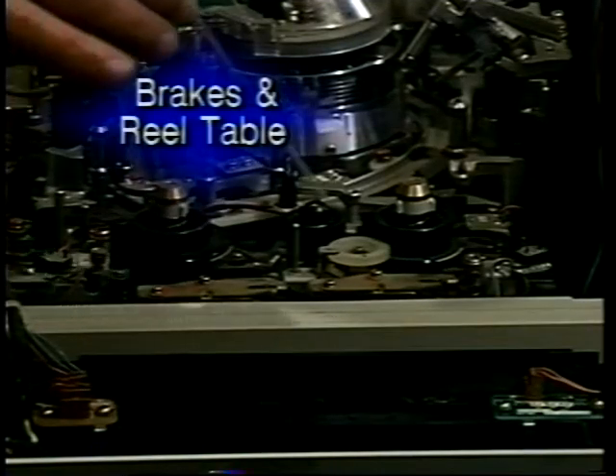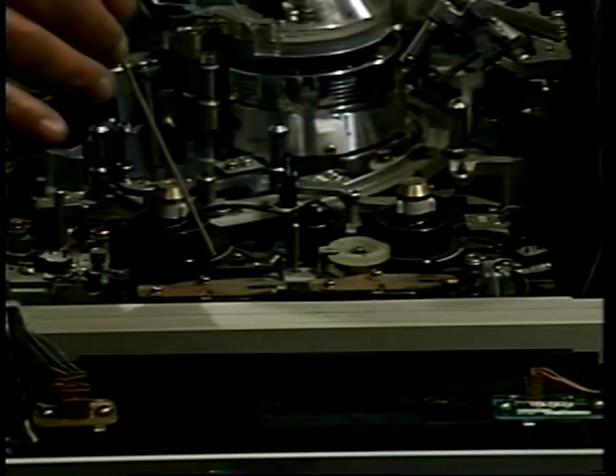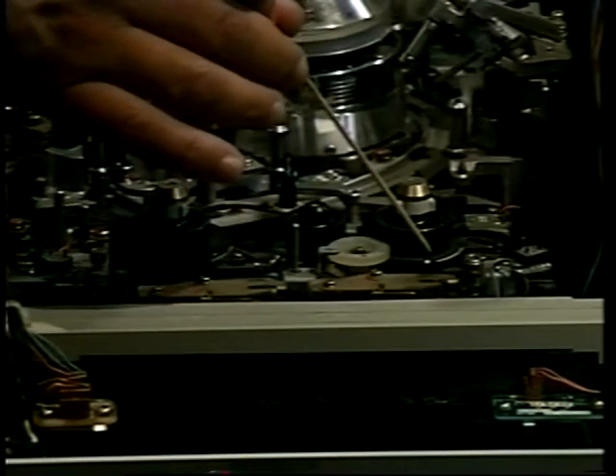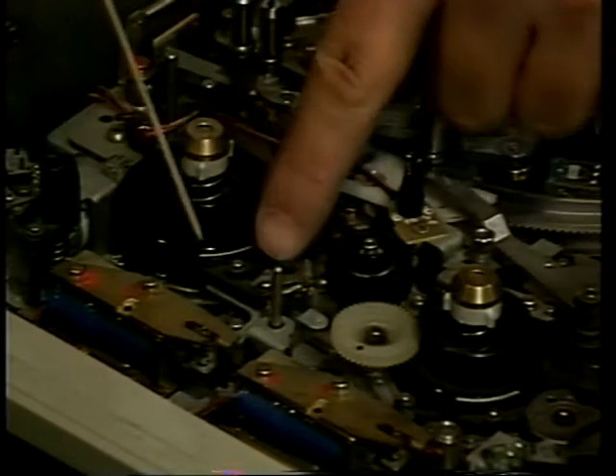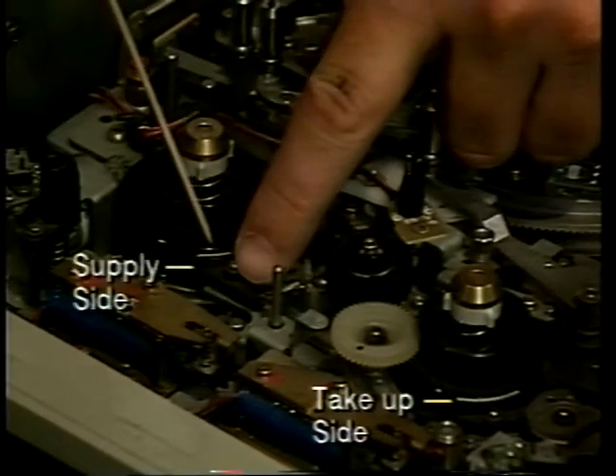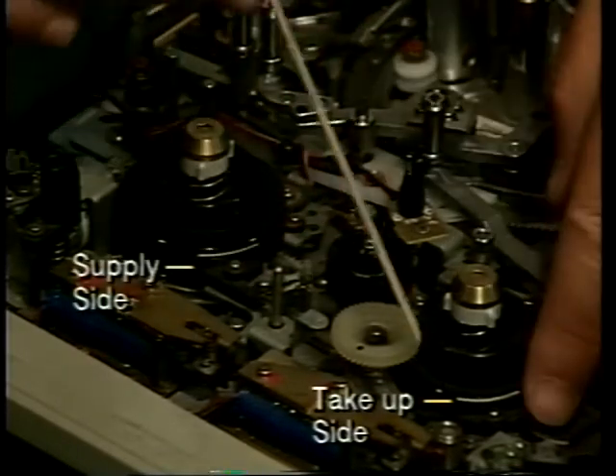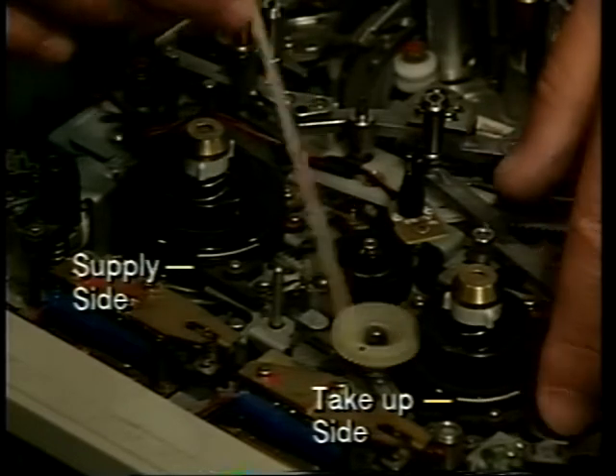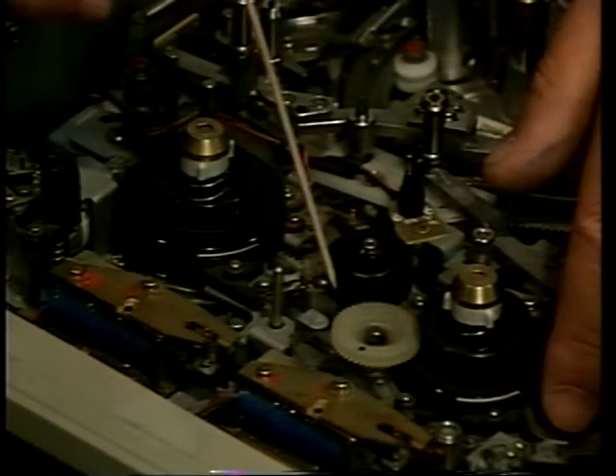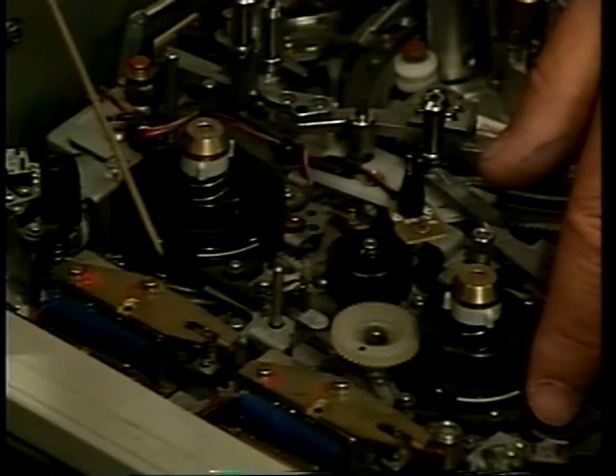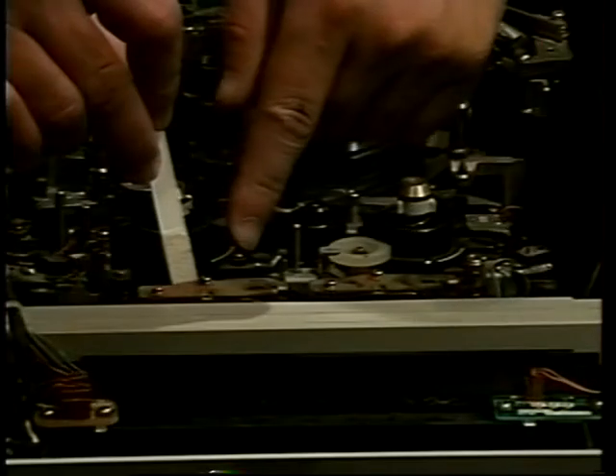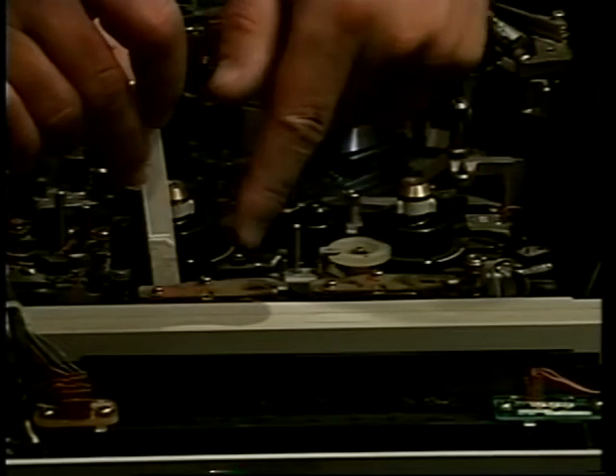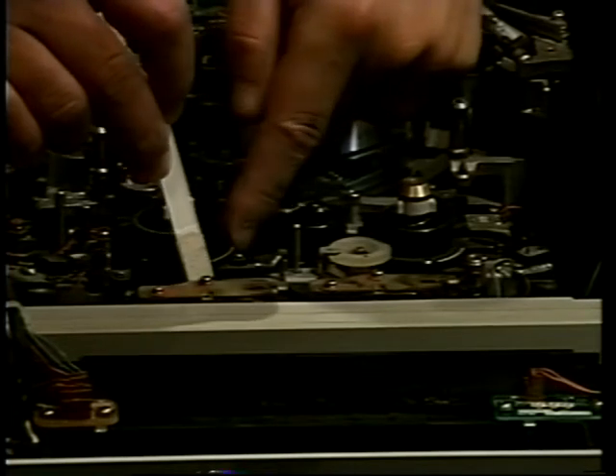Let's talk about the brake and reel table. In the older M2 units, such as the AU650, the reel table is set with 2 brakes above. These brakes need to be cleaned. They are the brake for the supply side and the brake for the take-up side. In addition to cleaning the brakes, the pads, you also need to clean the sides. Clean the reel using a cleaning stick dipped in a mixture of alcohol and water while turning the reel.